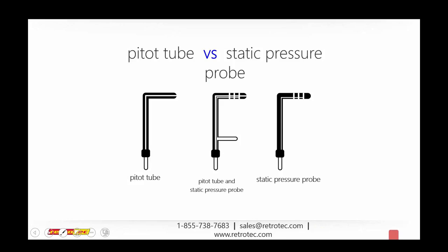So here I just want to differentiate, that's the word of the day, between a pitot tube with static pressure probe, which Joe told me earlier is the one that we see quite a bit of. It's very uncommon that you'll see just a standard pitot tube, and then a static pressure tube or probe. The static pressure probe is the one that we include with our residential duct testing systems. The reason for that is, as you can see, that these have holes on the side, whereas the pitot tube has a hole in the middle and on the side. The problem with this is, if there's air moving through a duct system, we don't want that air going directly into the tube and causing pressure fluctuations. What we want is to test pressure without that volumetric flow pushing through there and giving us readings that are not regular pressure readings.